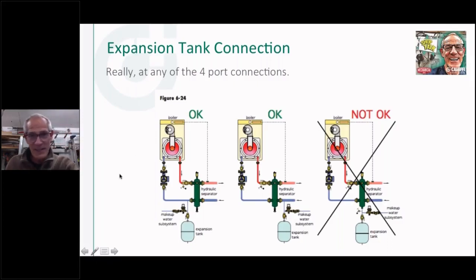So thanks to Dan Holohan, he kind of trained the industry, and John and other people, pump away from the expansion tank. Either move your expansion tank, move the pump downstream of it, or move the expansion tank down to the suction side of the circulator if it's on the return.